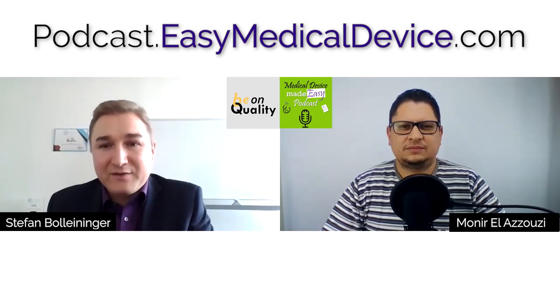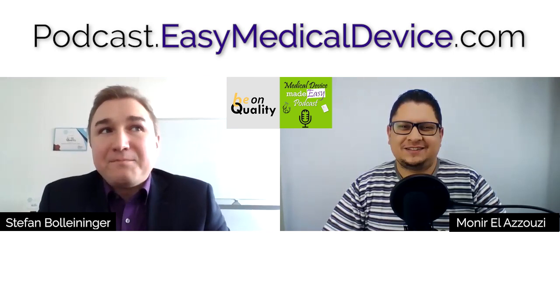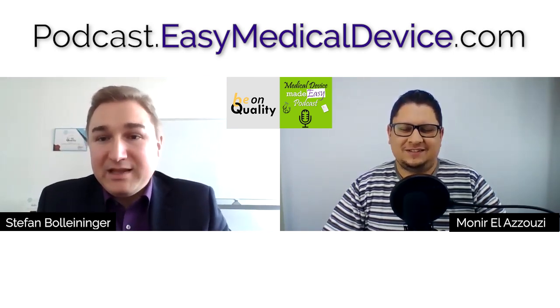If it's a harmonized standard, then it's the best idea to use it. So if you have a class 1M, 1S, 1R, 2A, 2B, or class 3 in Europe, then ISO 13485 is your friend. And if you are class 1, for example, is it mandatory to go for ISO 13485? No, it's not mandatory, but it's a good approach. Okay. So I'm not bound to anyone from the Standards Commission for that standard.